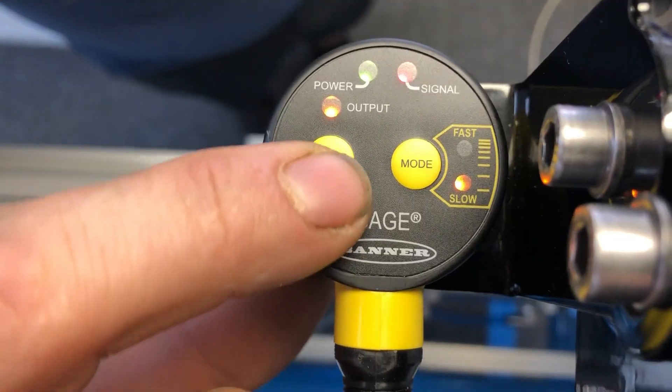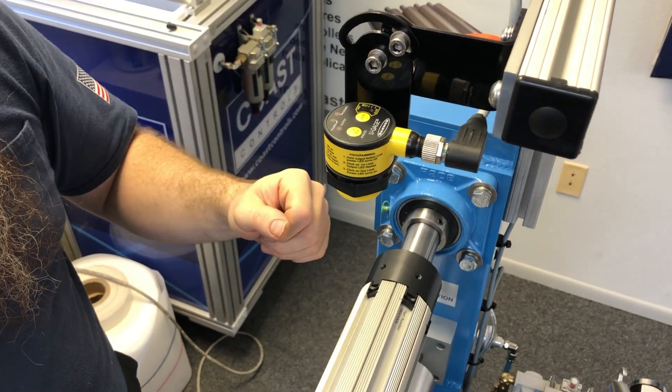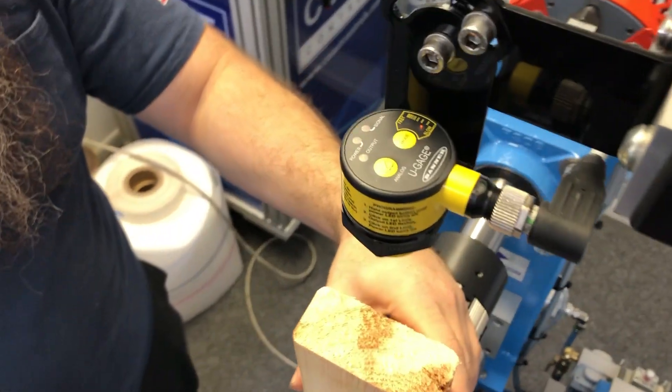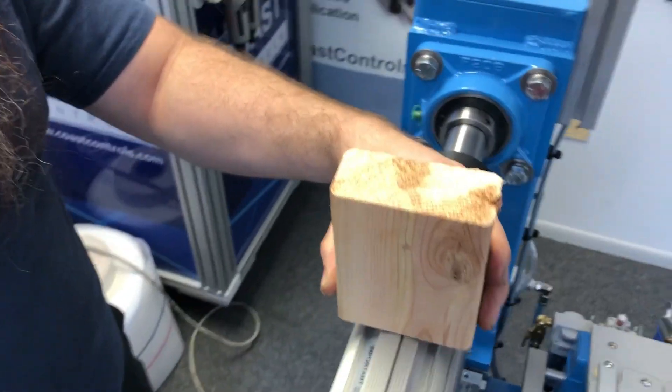Press the mode button for two seconds while there's nothing on the air shaft. Then do another quick press once while there's nothing on the air shaft. After that, place your wooden block so that the sensor can see it and press the mode button once again.